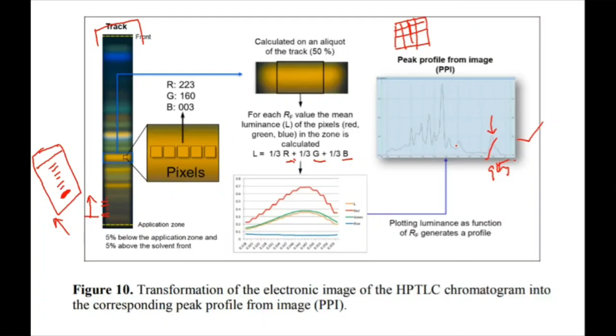Here the software is going to read the thickness of the light, and it will be translated into numbers, because the primary colors are red, green, and blue. How much red is there, how much blue is there, how much green is there is what is going to be captured, and then the captured image will be translated into a number. As the scanner moves from here to here, at every point the scanning is done. That's the reason why the densitometric information is translated into a graphical representation like this. The area under curve in every one of these peaks is what is going to give you the quantitative representation of the signal of a compound, which is actually giving you this kind of peak. In this way HPTLC works.